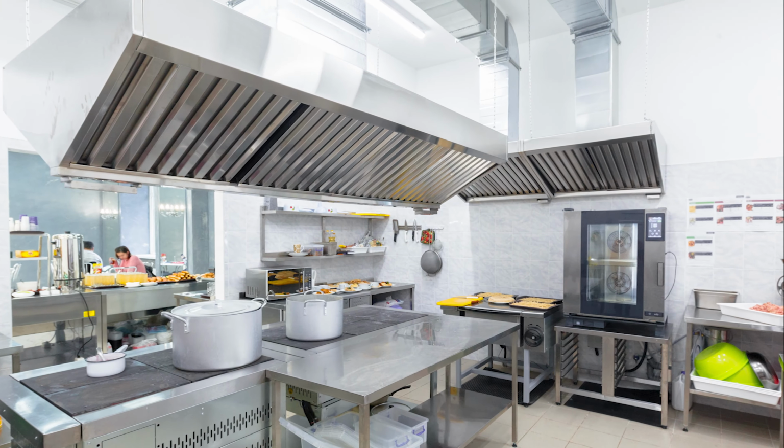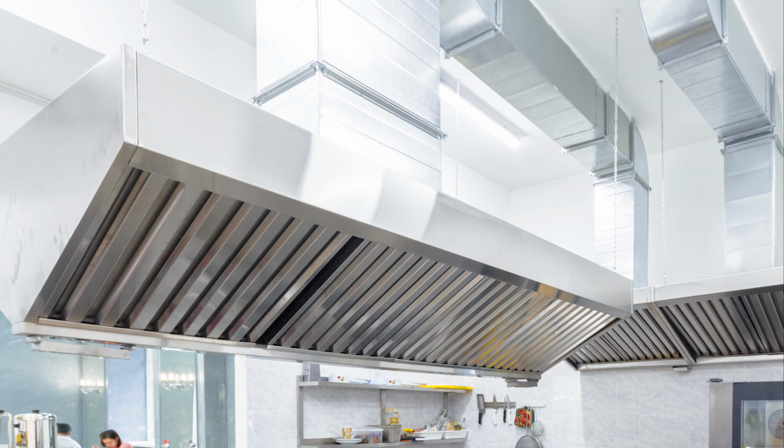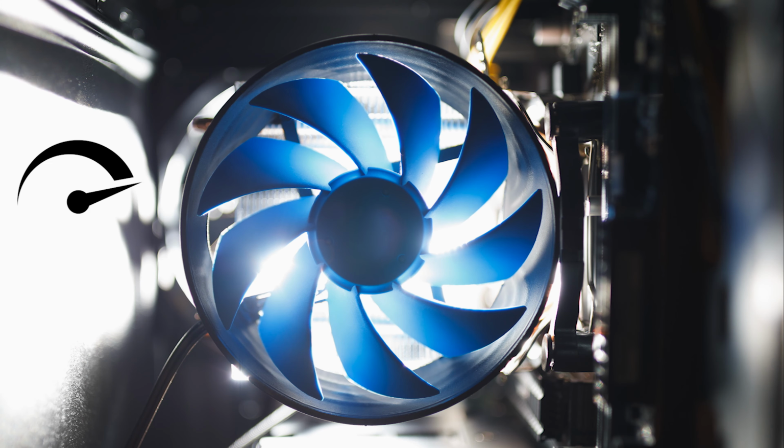In a commercial kitchen, for example, an extraction fan could have its speed controlled by a VSD, which takes readings from a CO2 monitor. As the CO2 level in the kitchen increases, it would instruct the VSD to increase the fan speed until the CO2 level returns to an acceptable level. Without this control, the fan would have to run at full speed all of the time to keep CO2 levels down, potentially wasting large amounts of energy.